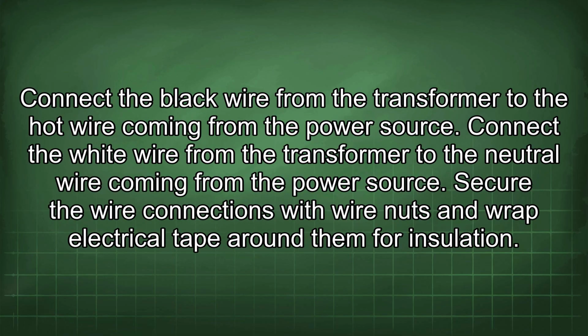Connect the black wire from the transformer to the hot wire coming from the power source. Connect the white wire from the transformer to the neutral wire coming from the power source. Secure the wire connections with wire nuts and wrap electrical tape around them for insulation.